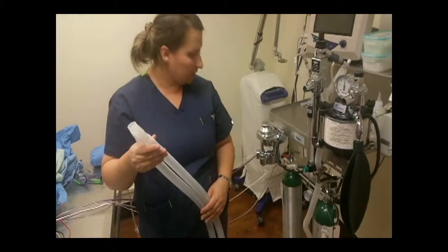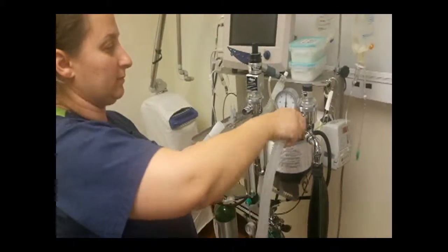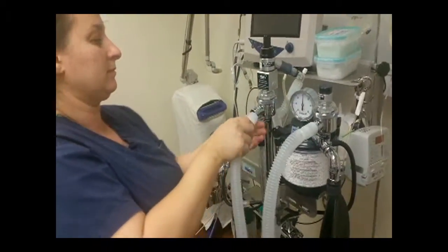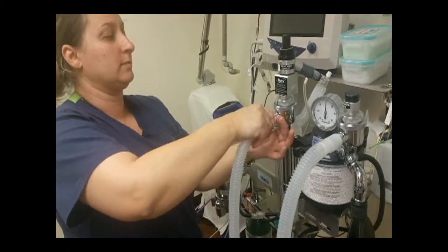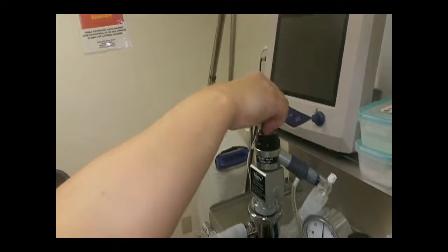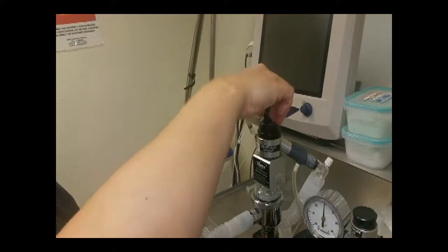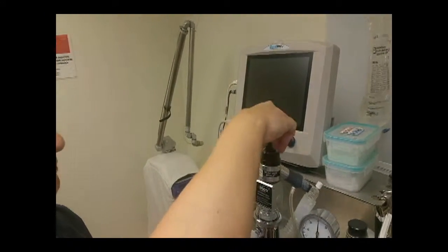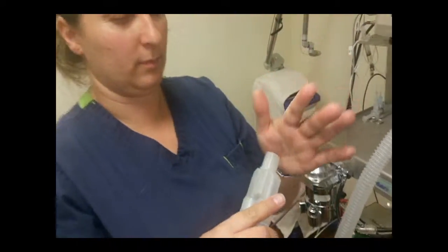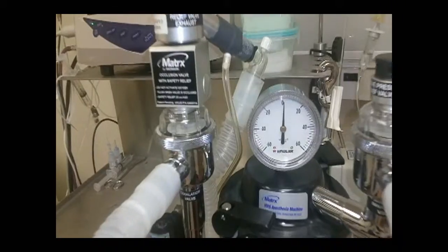Dear alien friends, this is how you pressure check our rebreathing circuit, connecting to unidirectional inspiratory valve and unidirectional expiratory valve. I'm gonna close my pop-off valve all the way down. Then I'm gonna cover my Y piece all the way fully.